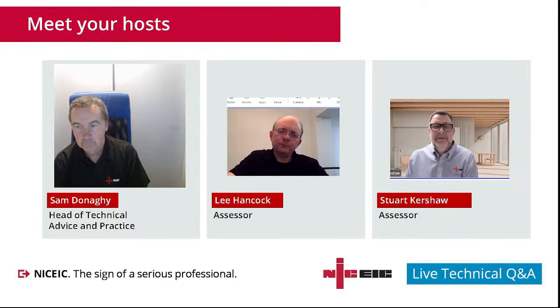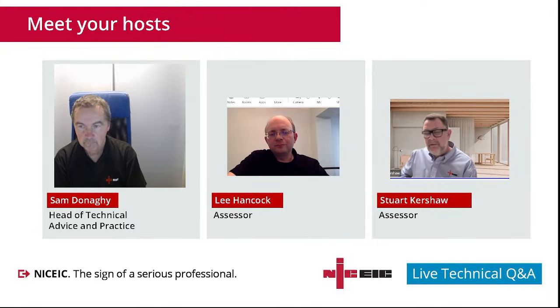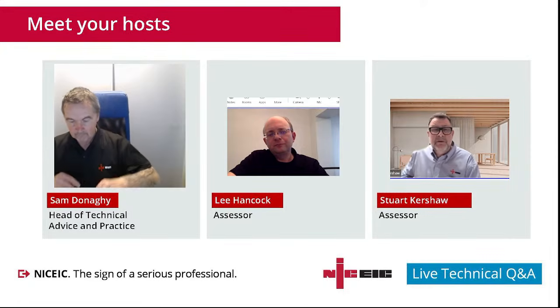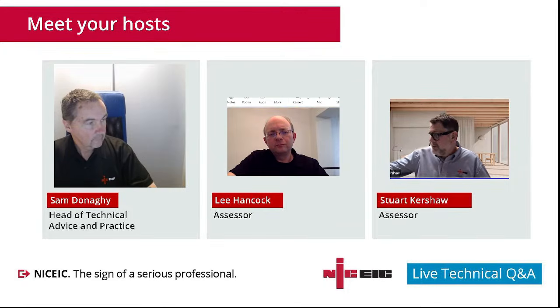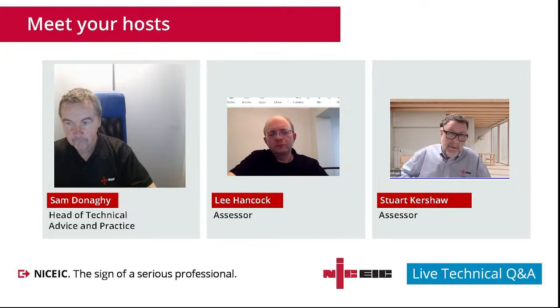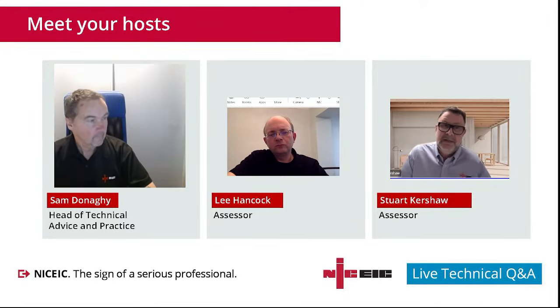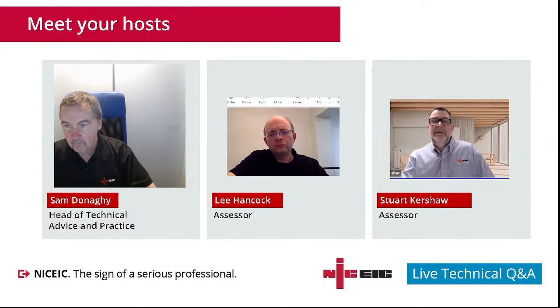There's other options for limiting live testing anyway, isn't there? With electricity at work regs, so if all the other relevant tests are carried out for initial verification and R1 and R2. Calculate ZS. Yeah. I'd be interested to know the answer, Sam, if you could ask your colleague, because he may have a better angle at it. But is it really necessary to obtain a ZS? Or could it be recorded and then marked on the EIC in the comments bit at the end that ZS has been obtained by calculation from R1 and R2 and the ZDB or ZE, whichever is most appropriate? It is acceptable to do it by calculation. We need to measure to make sure that there is a CPC if we're reliant on ADS.